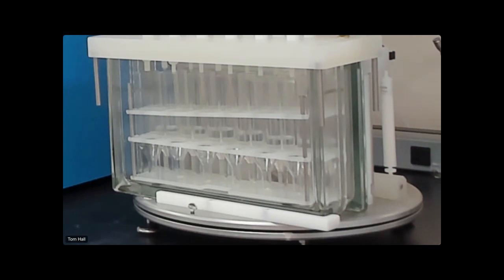How many mils have we got, Rick? 22 mils. So this takes 8 minutes because we're doing it at a flow of 5 mils a minute because of the back pressure that the carbon gives the system. You can try to do it at 10 too, but sometimes you'll get leakage or overpressurization.